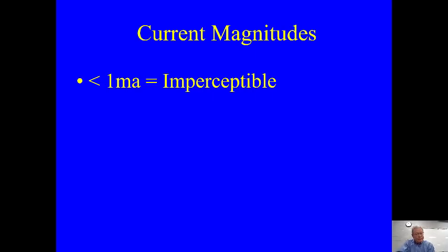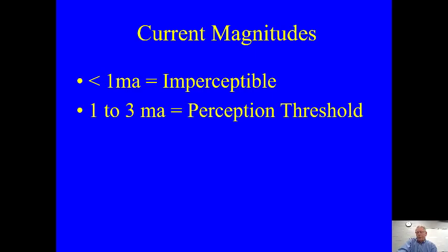Is that good information? Heck yeah. 1 to 3 milliamps is the perception threshold. I don't know if you've ever touched an electrical cabinet or a home appliance and barely felt a tingle, something's wrong. Probably that motor's grounding. If you've got a garbage disposal on a stainless steel sink that's going to ground, but it's not grounded enough yet to trip the breaker, it'll give you a tingle.